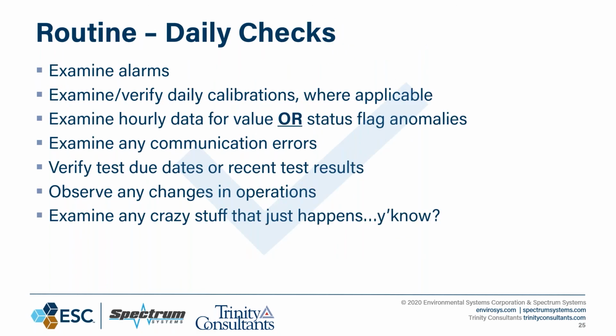And finally, we come to our daily checks. I'm going to direct this part of the conversation to the people who routinely look at their DAS. On a daily basis, you should be examining your alarm screens, looking for those alarms that are going to definitely constitute an exceedance or a downtime period. Be aware of them. You should be examining and verifying that your daily calibrations are occurring when you expect them, that they showed up a short time after the calibration was complete, and you should be examining hourly reports for both value and status flag, looking for anomalies on either.